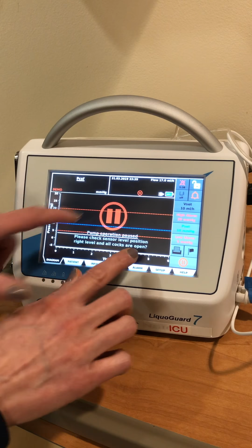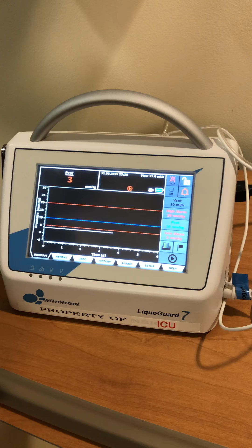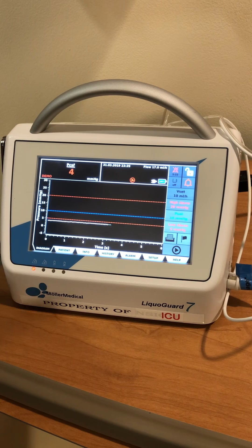So if for some reason you're not getting your volume, your CSF is showing 0 for that hour, make sure that you've hit play. Okay, so this was made in Europe, so it's a little backwards. We're used to it being the other way around. So that is pause, and it'll say on the screen, so you want to hit the pause button. Now you're in play when you see that going. So always make sure you're in play, that it's actually running.